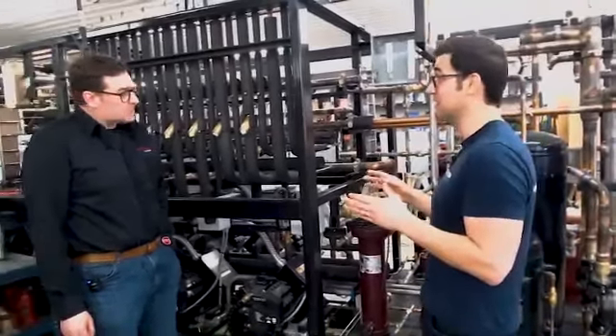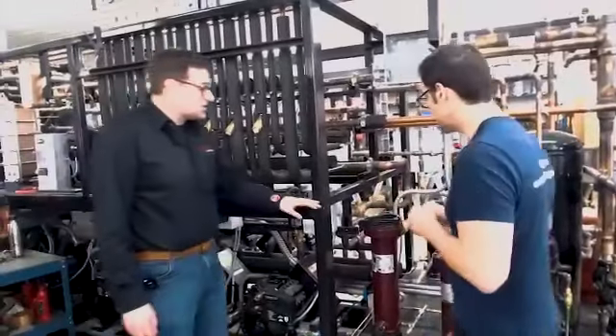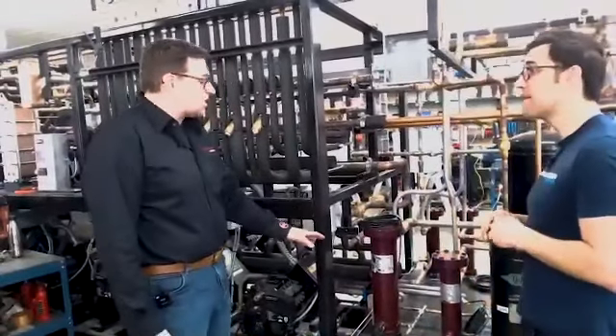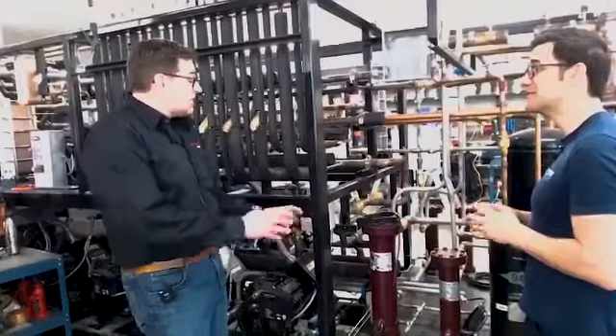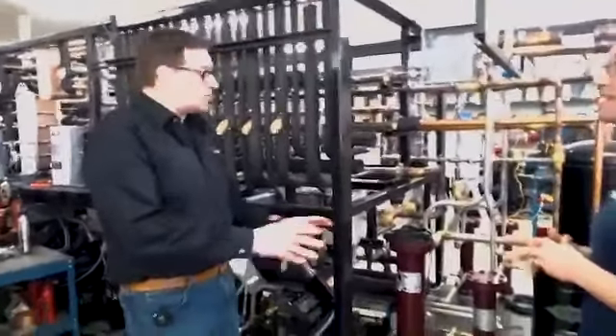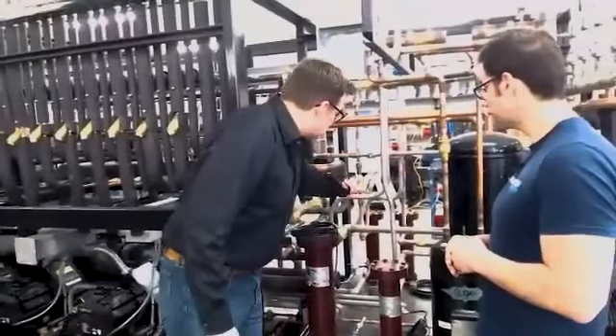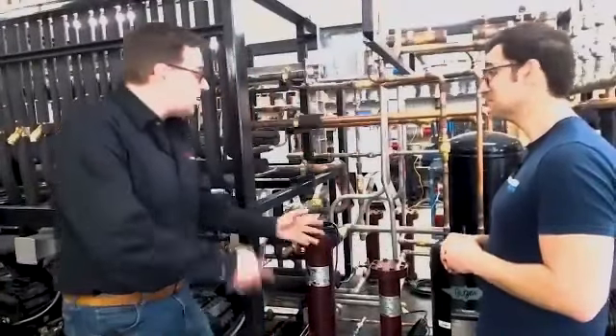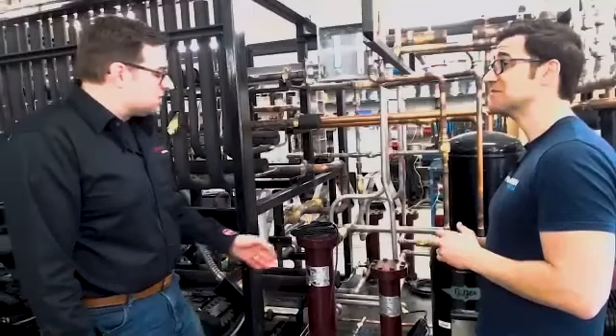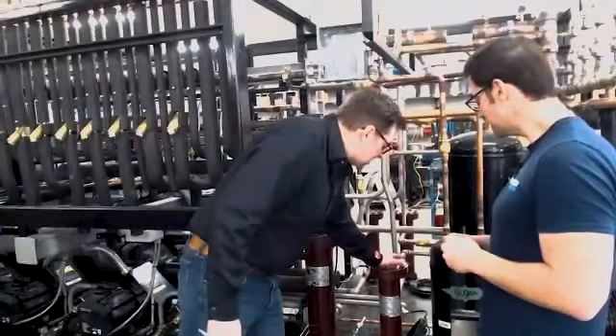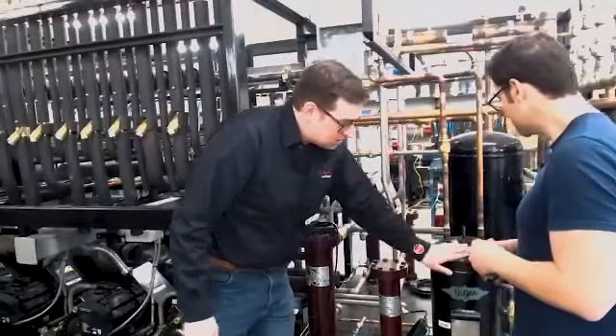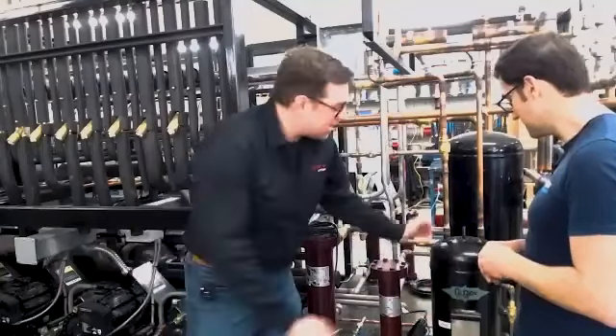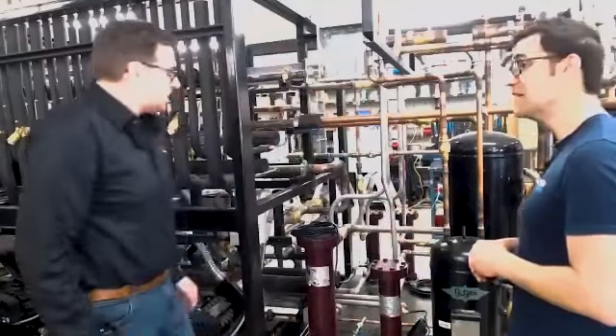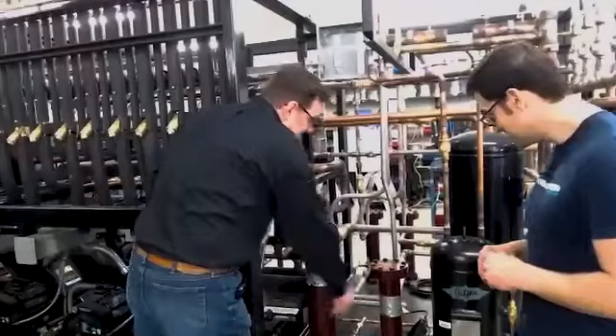But this here, you guys got a really cool design and way to drop out the compressors without having to cut anything. Well, the last thing we want is for a service technician working on the job site to have to cut anything out. It's just so problematic. If you see what the oil separators are from our engineering team, we can put all these underneath our arm and walk away with them. So that's something the guys always consider. Heavier components, we move closer to the edge of the rack so we can tip and get them out. Lighter components, we move more inside.